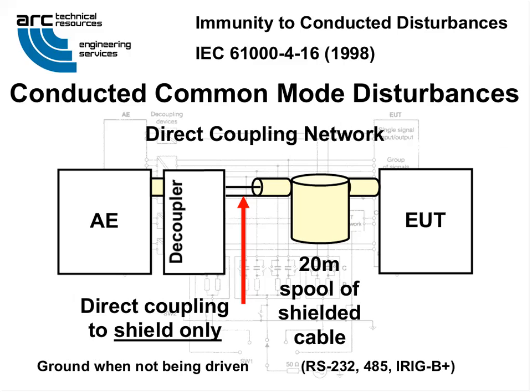For direct coupling, the EUT is connected to a 20-meter spool of shielded cable like RS-232, RS-485, or IRIG-B. The far side of the spool is connected to a decoupled auxiliary equipment. That's often optically decoupled, by the way, with a battery and a small opto isolator. The idea is you just float that in, and then the auxiliary equipment is not affected by the disturbances. It's been opto-isolated. And the reason there's a battery is because it doesn't leak into the power supply that way. So you can make sure there's no interference that gets to the AE. You want the AE to be removed from interference, but be able to see and talk to the EUT to determine if it's being interfered with.